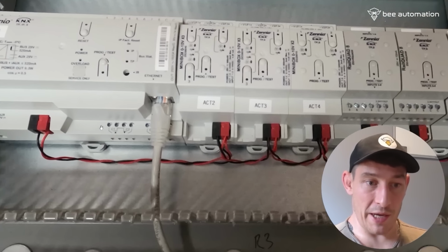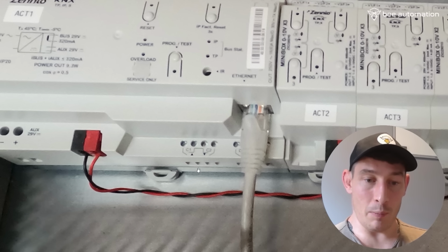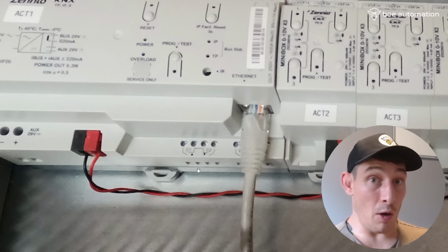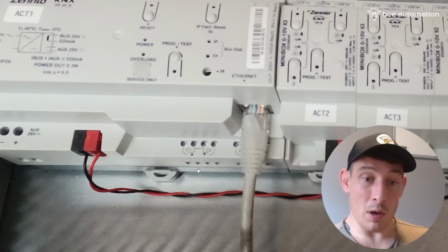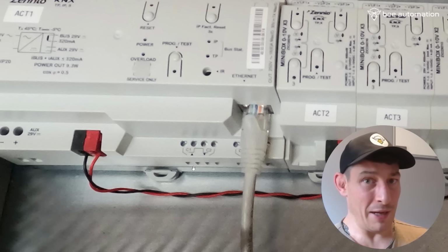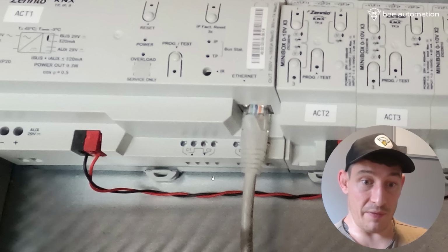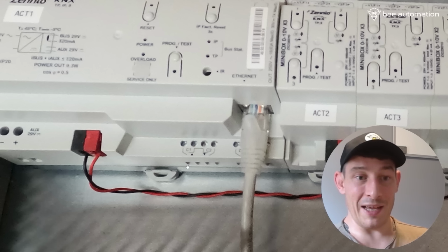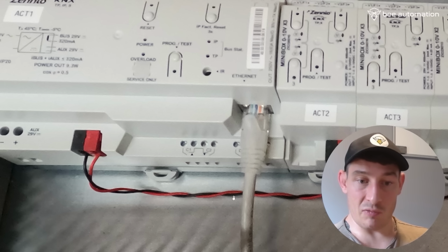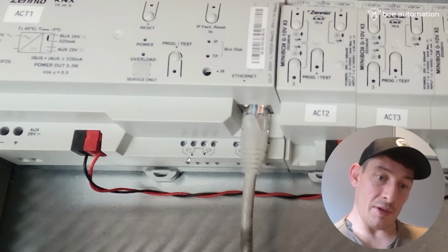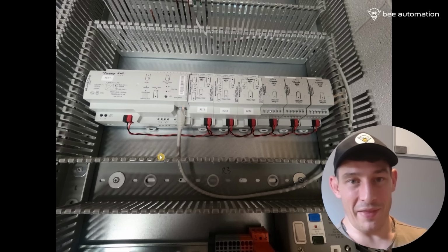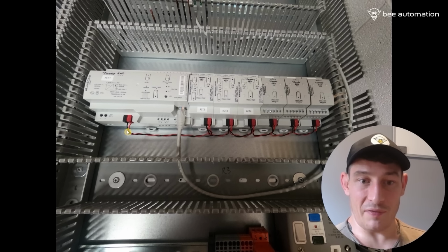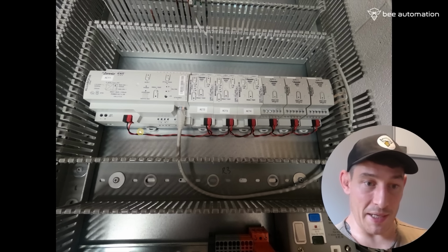But this module here, where there are these relay outputs, you might be switching low voltage, like 230 volt loads. Again, they're not necessarily noisy, so very low chance of interference, but that's where you might be a little hesitant. It's not the best angle here, but these links run along the back plate, raised up above the back of it. So there's never any issues, but it's far easier, and saves space, than using lots of the green cable here.